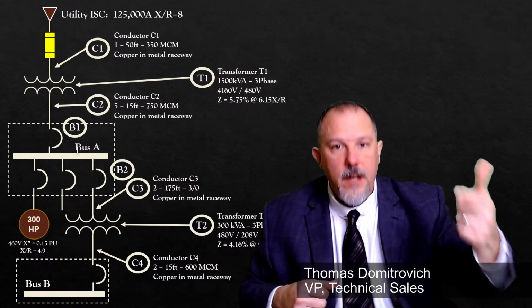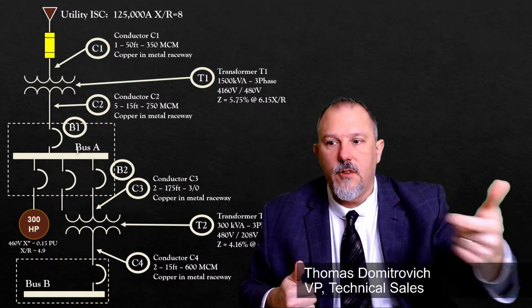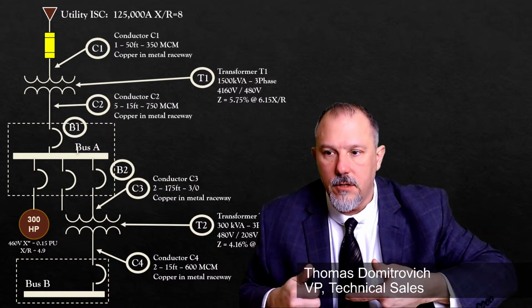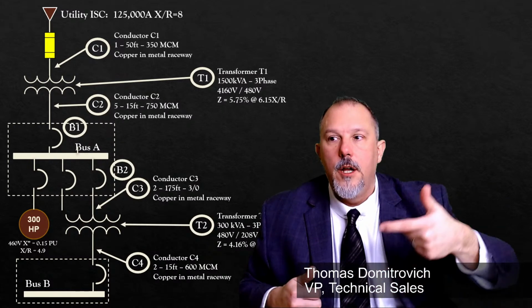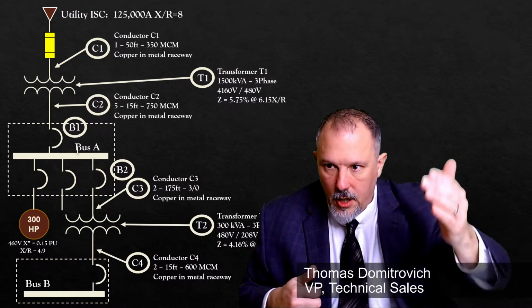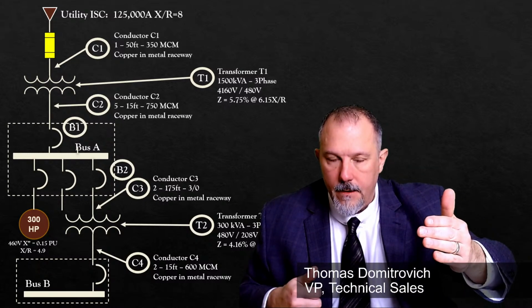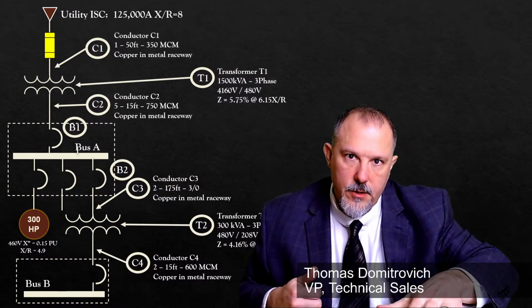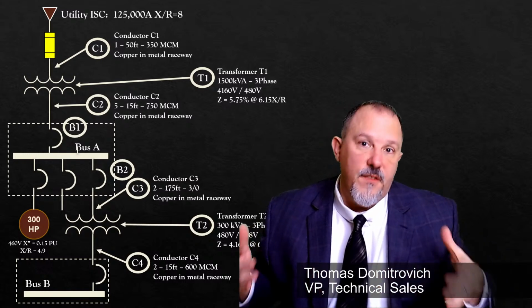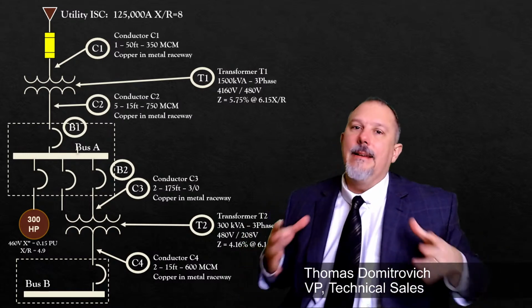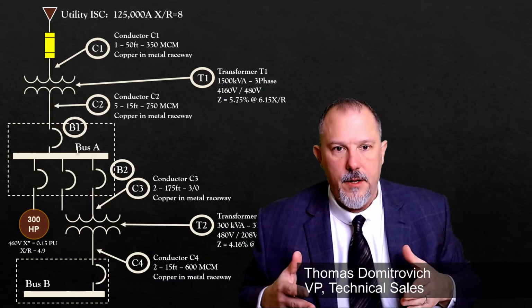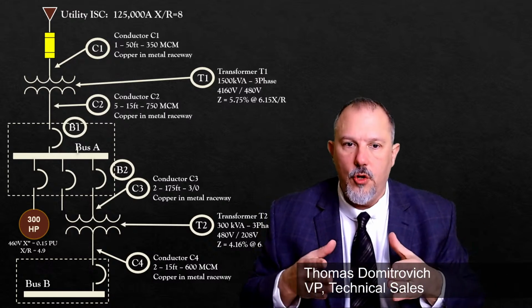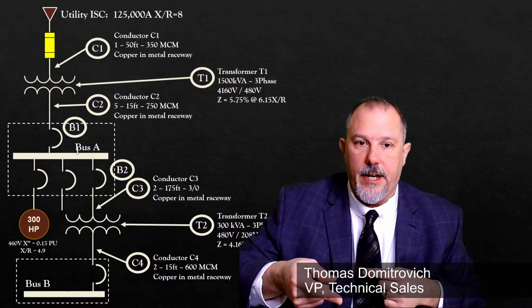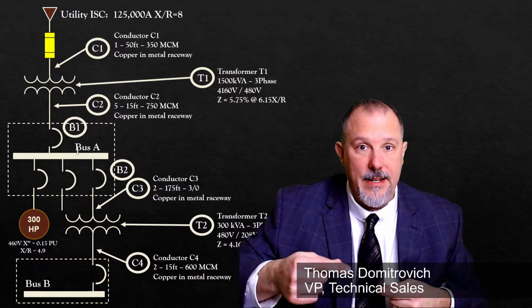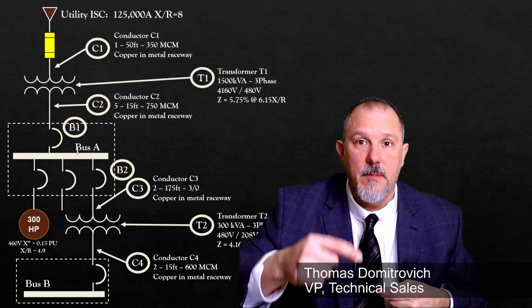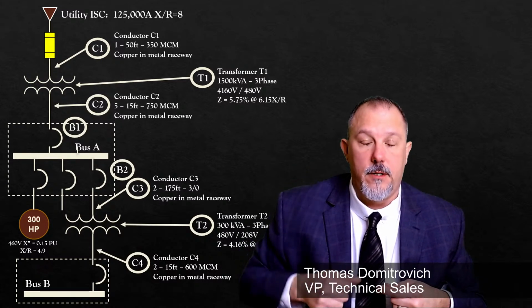Now, the figure in 700.32 and 701.32 and a few of the others don't show those other circuit breakers or overcurrent devices because they could be fuses. But the point is that if you have a miscoordination, then you drop more loads than you would have if you had coordinated. And my point is, you can't make that determination if you don't calculate fault current.